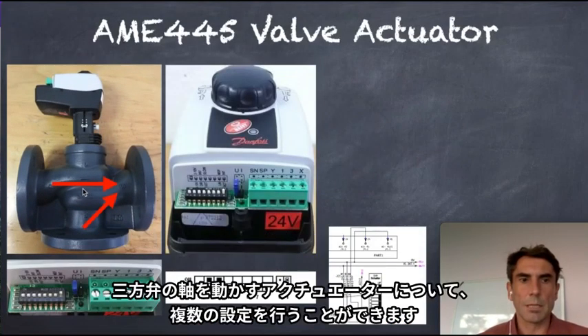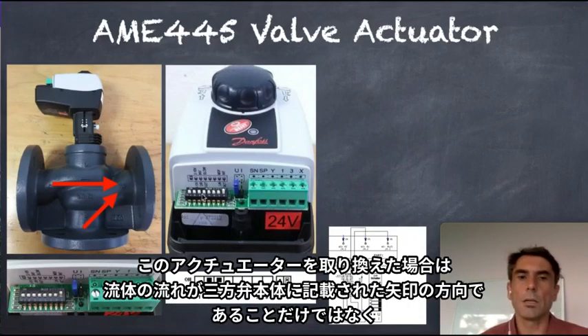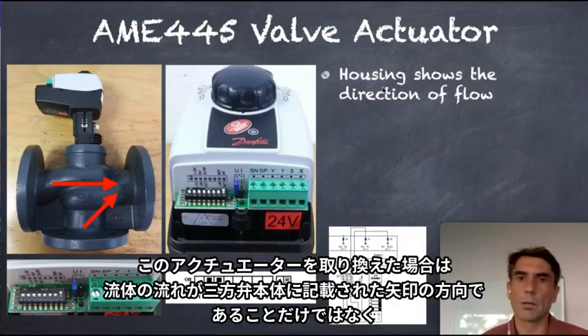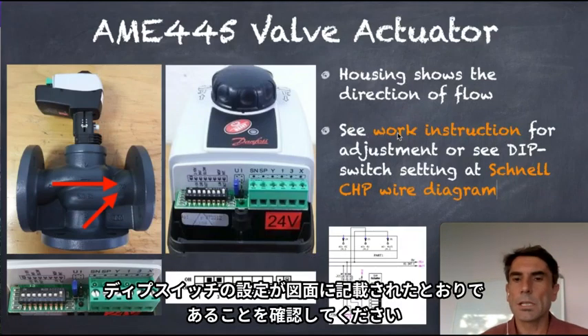On the valve itself, we have this actuator. The actuator has different options to adjust. Always important, if you get a new actuator motor and you have to replace it, please ensure that the adjustment is exactly on the requirement. Okay, the housing direction is like that, it shows the arrow, but on the motor, please check the instruction. I will send it to you as well.